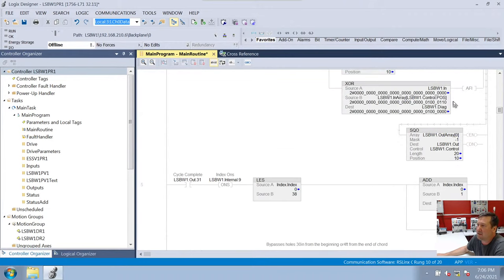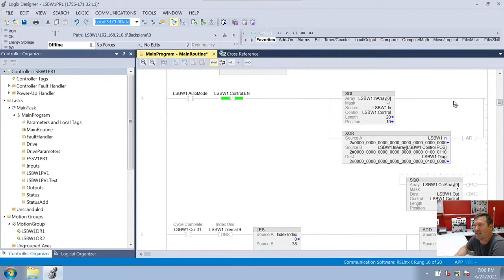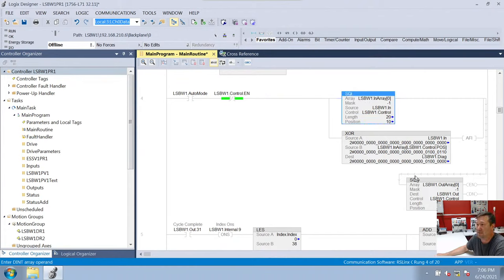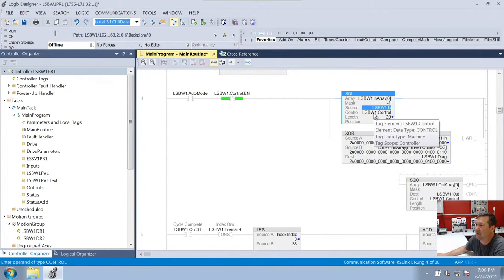The next rung is where I'm going to start knocking myself pretty hard. If we just look at this rung, especially 20 years later having never seen this setup before, we're not going to have any earthly idea what this is doing. This is a sequencer input instruction and a sequencer output instruction. You tie these together with this control bit. I noticed this is a user-defined data type. Let's go down to our assets and then user-defined.